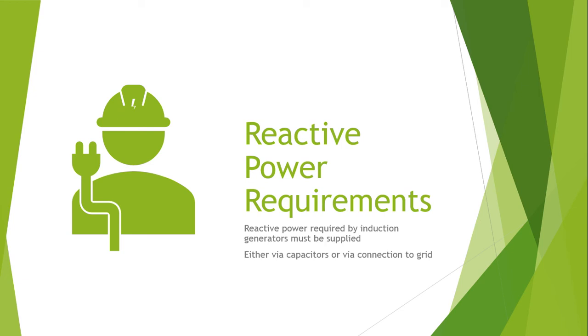A capacitor bank at the load side locally generates reactive power, thereby reducing the overall reactive power demand as seen from the generator side. The major limitation of the induction generator is that it requires reactive volt-amperes from auxiliary equipment — an induction generator cannot generate reactive volt-amperes.